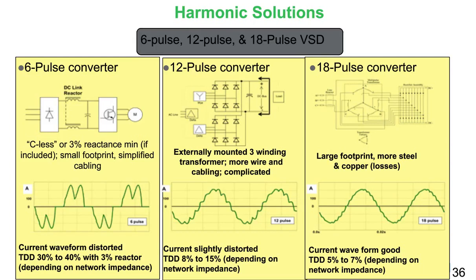So if we move our discussion to the 12-pulse converter, the current is slightly distorted, TDD at 8 to 15%, again depending on network impedance. But you can see the waveform is improving. However, it is still fairly choppy, as shown in the graph there. And if we move to the far right, we can get a comparison against an 18-pulse converter, which shows a current waveform good to TDD 5% to 7%, again depending on network impedance. But the waveform does get much better. However, there's still some slight spikes in that waveform. And your TDD is, again, still at 5 to 7%.